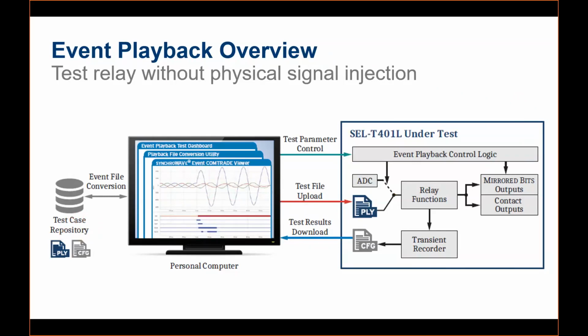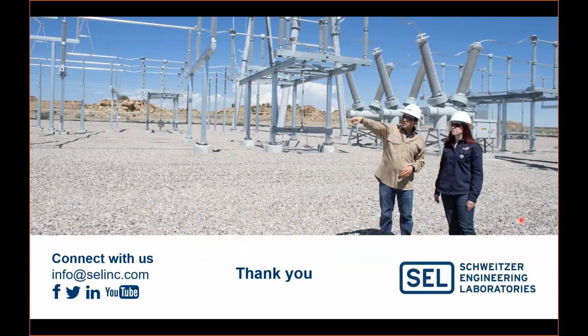It will convert the file and send it to the relay, and the relay will itself simulate that COMTRADE data that you have. Originally, it is using the ADC data, but in event playback mode, it just switches to the file you have loaded as a COMTRADE file. So the relay will evaluate all the currents and voltages from that COMTRADE file and make its decisions. You can compare these decisions with the relay at the field, and compare how fast the T401L is as compared to the relays available at the sites, and also how dependable it is. So this is a testing facility available inside the relay without using any test set. And that's all from my side. If you have any questions, I'll be happy to answer. Thank you very much for your time and attention.